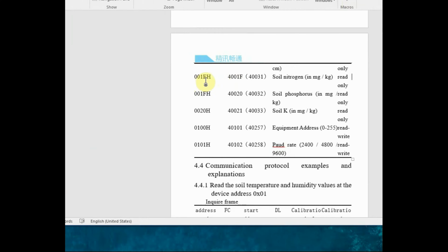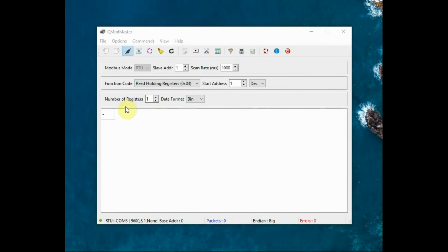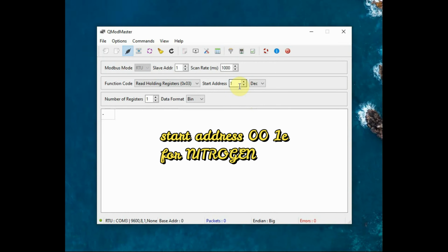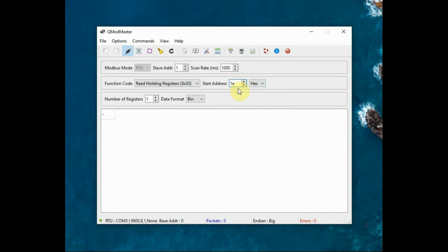And the most important is the address of the registers. 001E, as per the data sheet, 001E is the address of the nitrogen. So feed in 1E, and after selecting hex, number of registers 1, go to command and then click on read write. Every time you have to click on read write. Change the format to decimal. You get directly the decimal value.